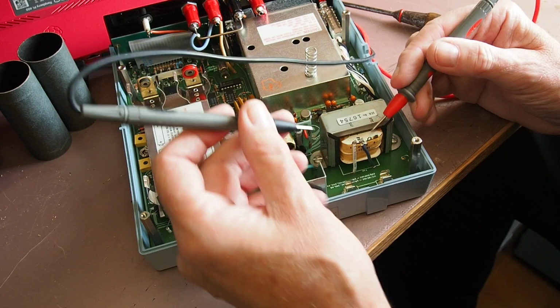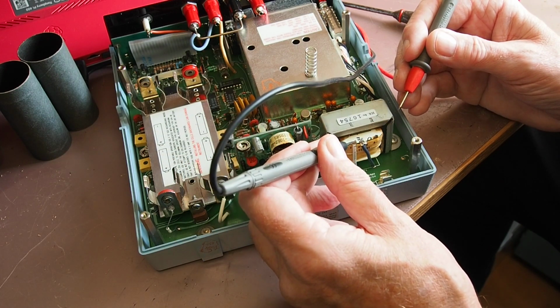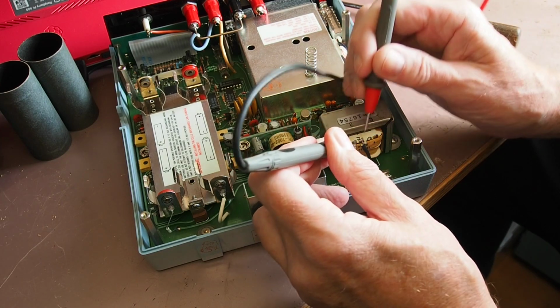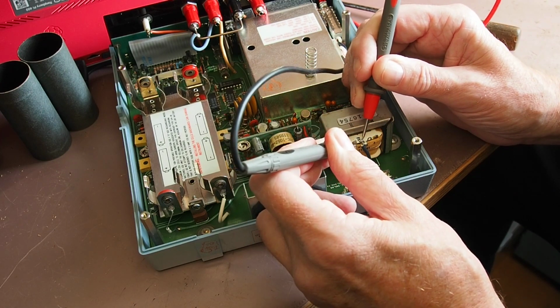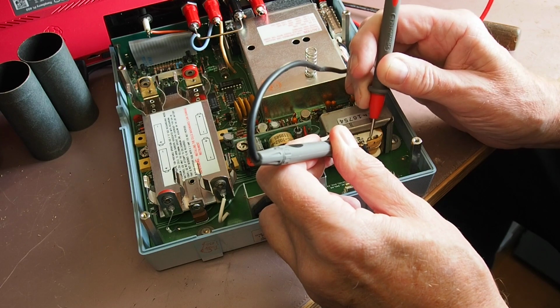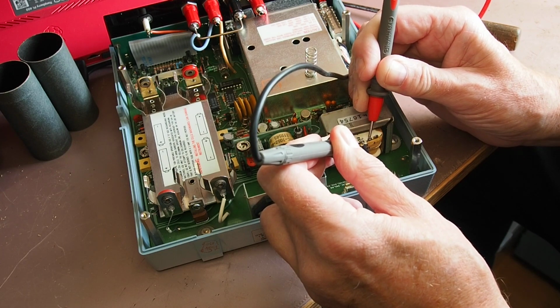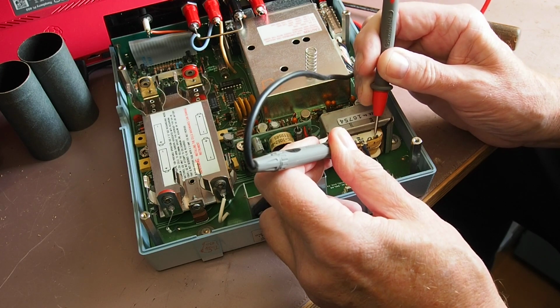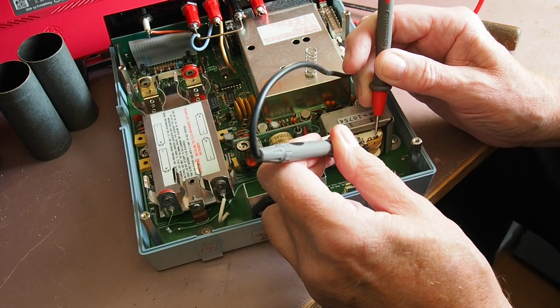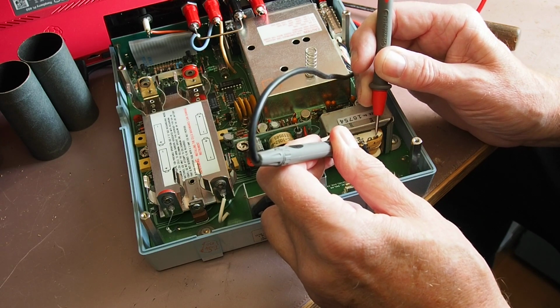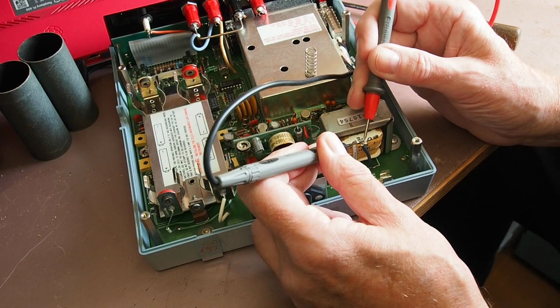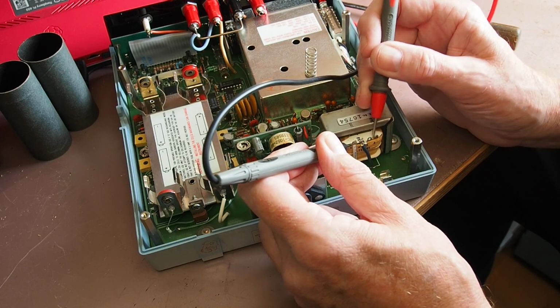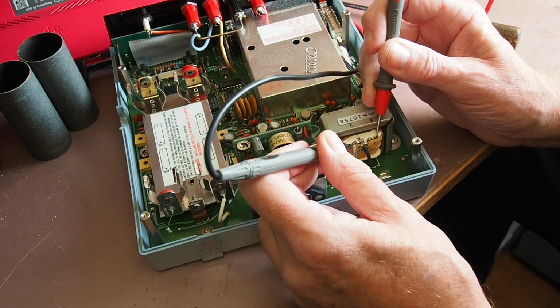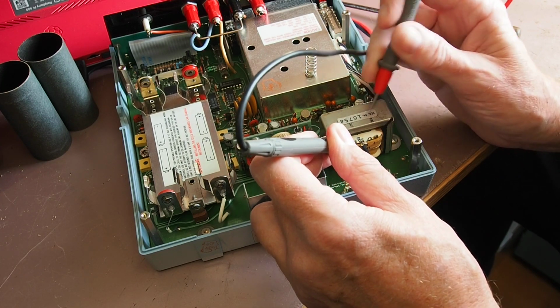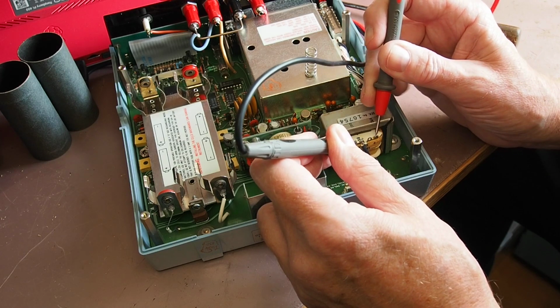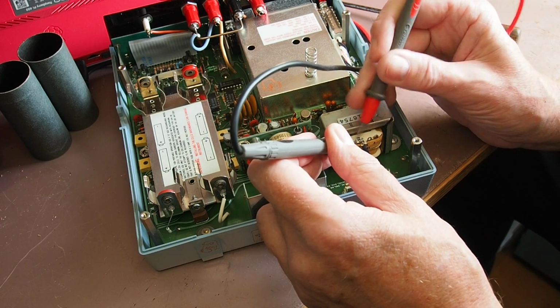Now there's a couple of other connections on here, so I'm going to leave my first probe on there. This first tap is 109 ohms. What's that one? That's 316 ohms, and that one is about 360 ohms. So I'm going to hazard a guess that those are 120, 220 and 240 volt taps. I'll do some maths, but I suspect we might be able to make this work off European mains voltage. Yeah, so that appears to be the taps.